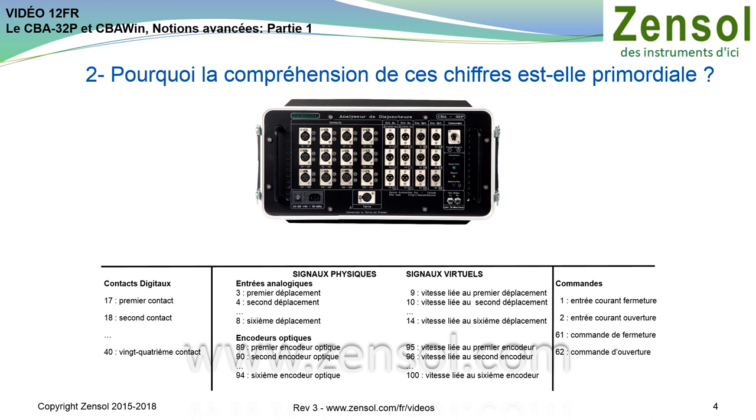This information allows you to calculate the speed of the moving contact at any given moment. By plotting all these values calculated at each instant, we obtain a new curve as a function of time. This mathematically calculated curve is called a virtual signal, which we need to visualize like any other synchronization signal. Cbawin actually has 14 virtual signals, which are shown on this slide.